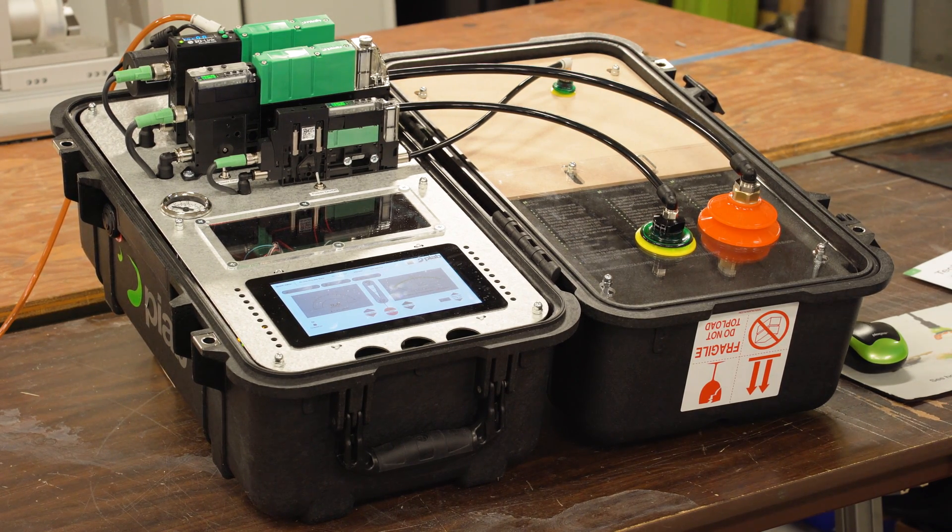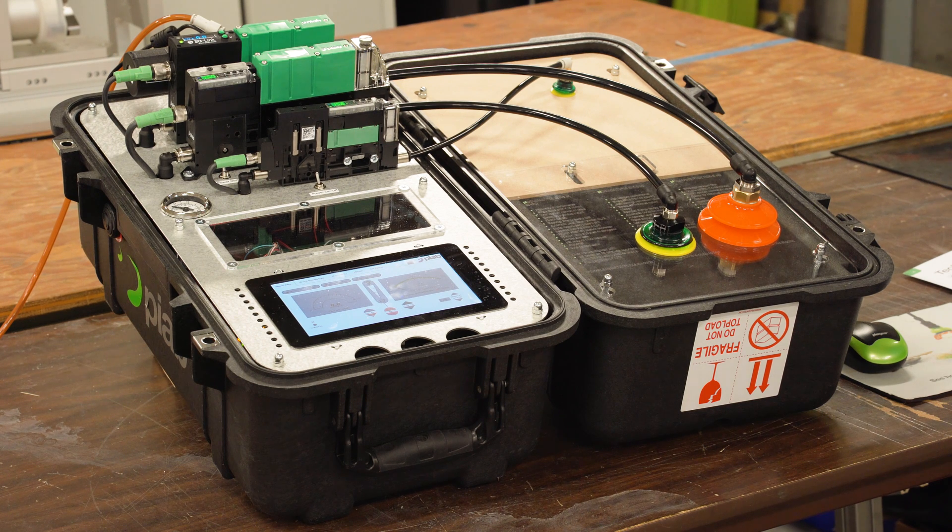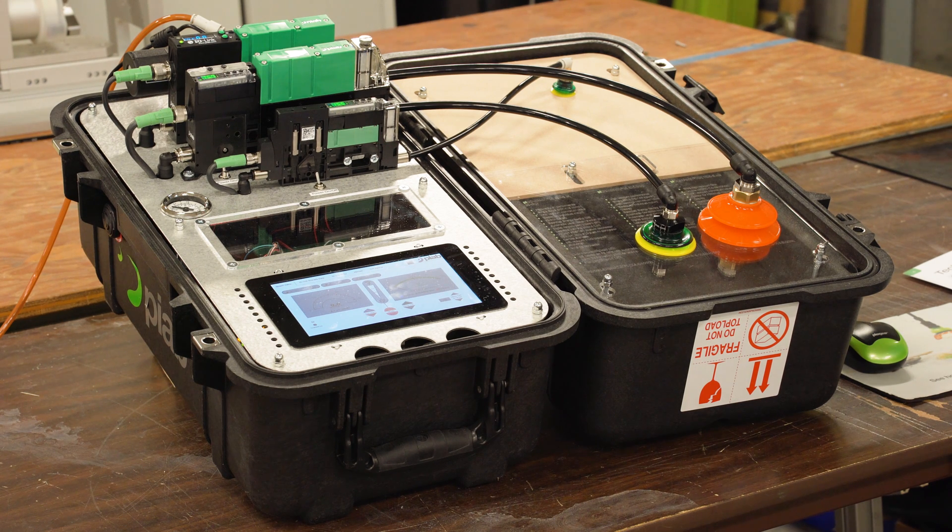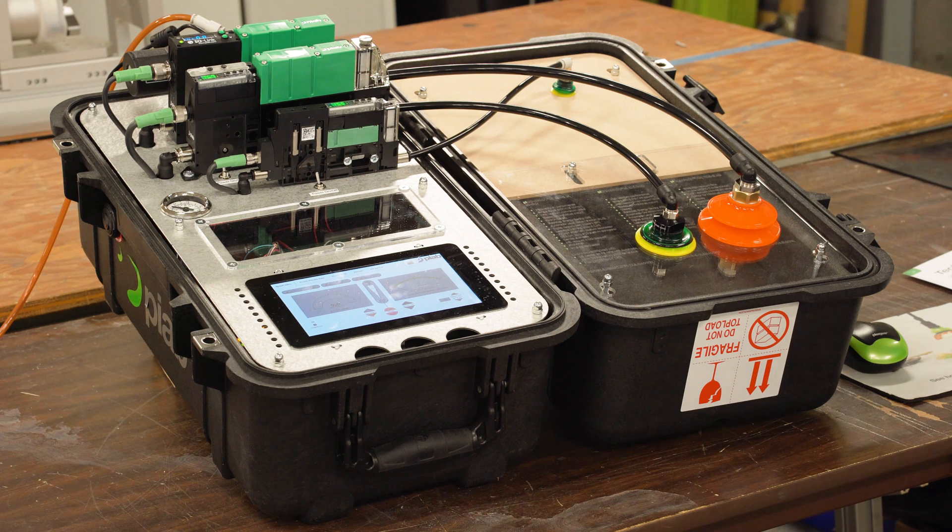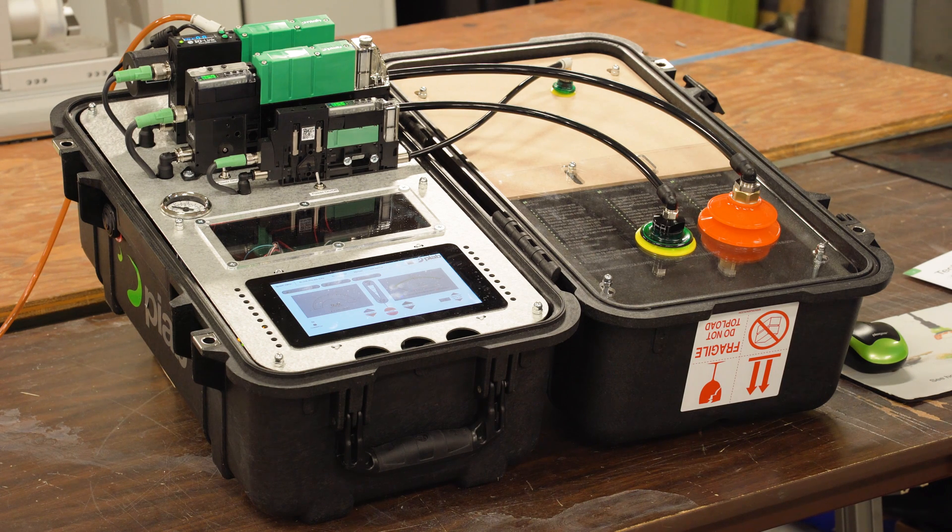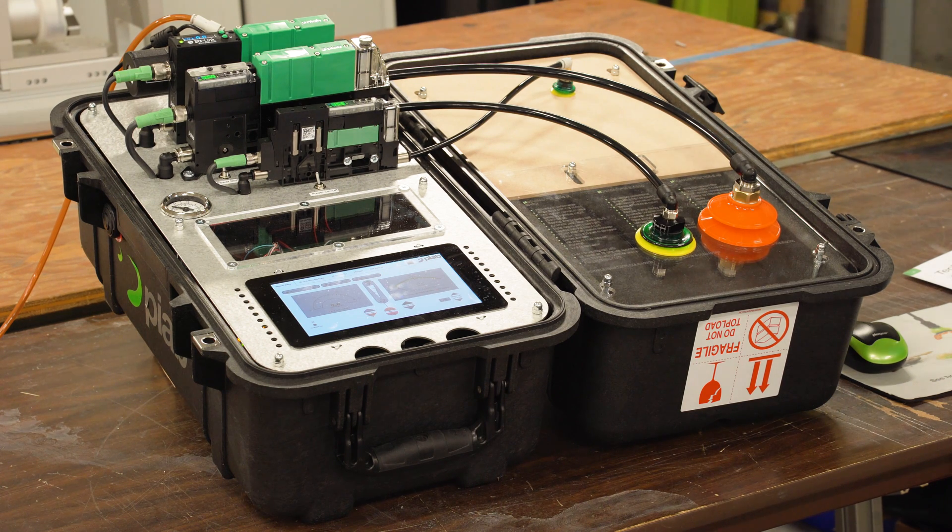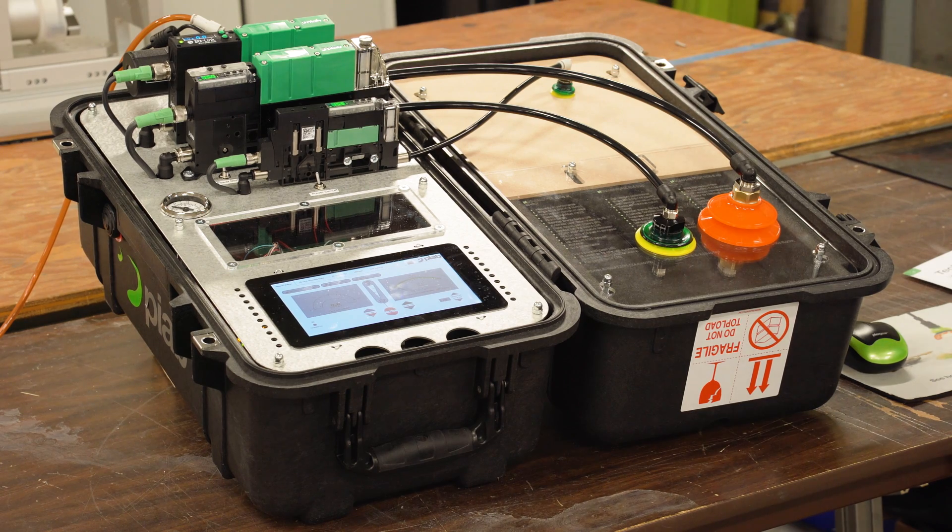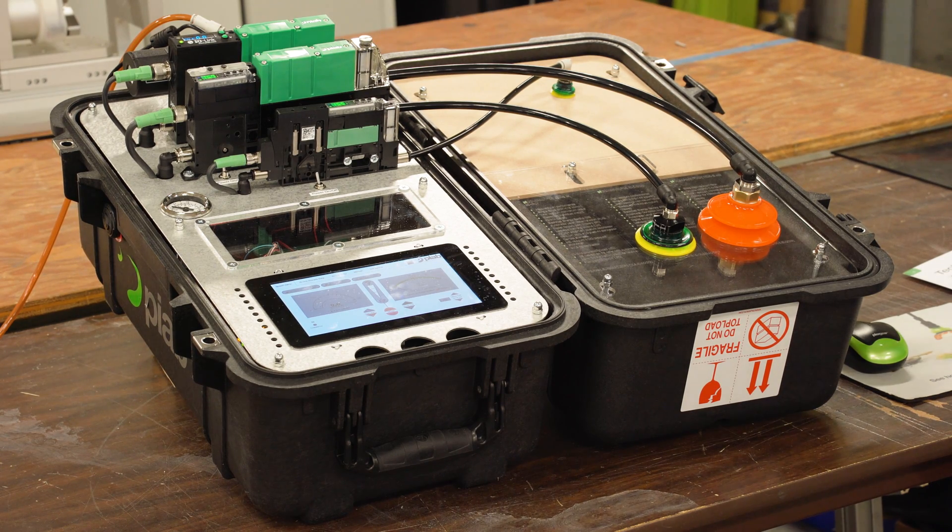But now it kind of gives you a little bit of a predictive maintenance, almost. If your operator's saying, hey, this thing's purging air all day long, well, you're able to come back and figure out, oh, the suction cup's wearing out, I've got a loose fitting, something along those lines.